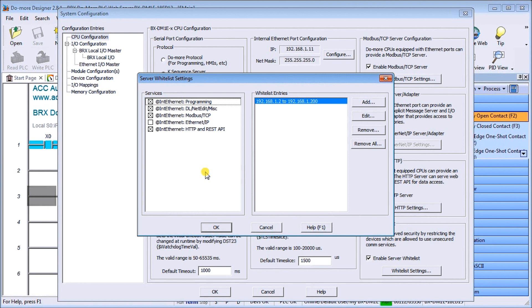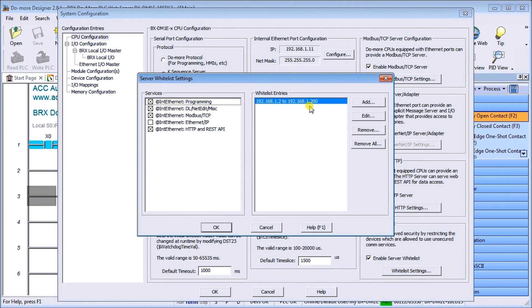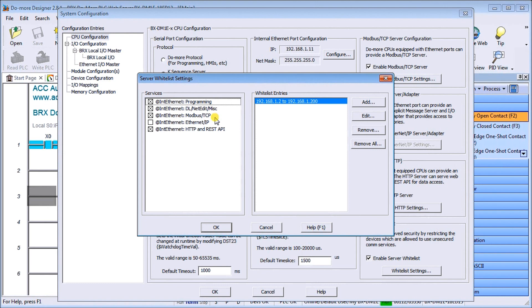In our case here we have each service highlighted and then we specified a range of addresses from 1.2 to 1.200 in our network. Basically all the computers on our network will be able to communicate to this BRX. It's a good way of limiting who can actually communicate or program or do Modbus TCP, Ethernet IP, or HTTP and REST API.